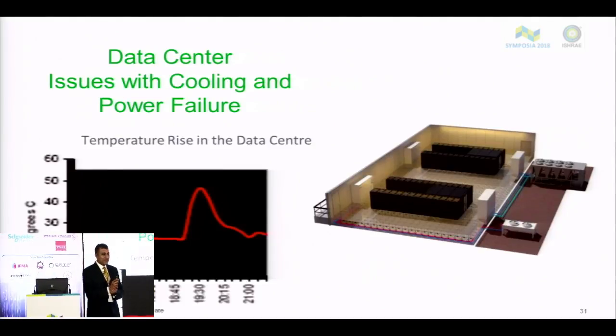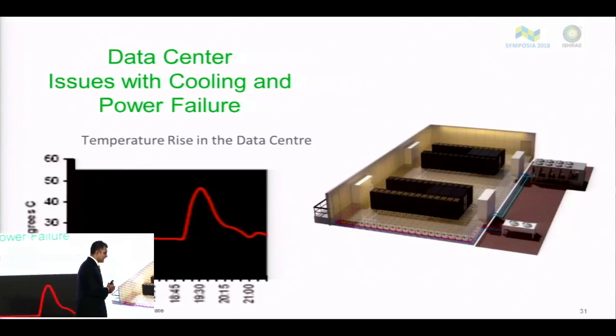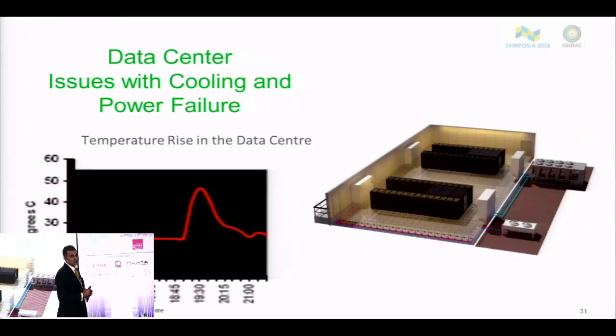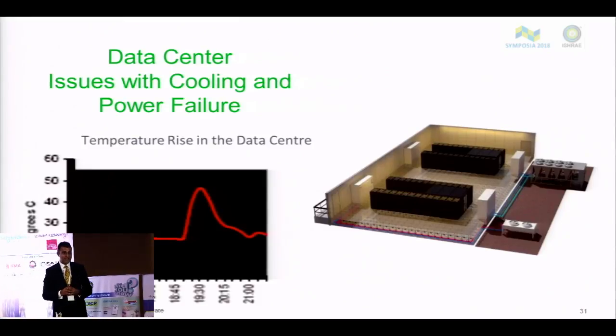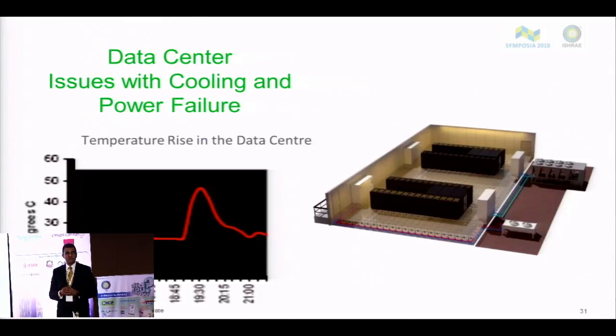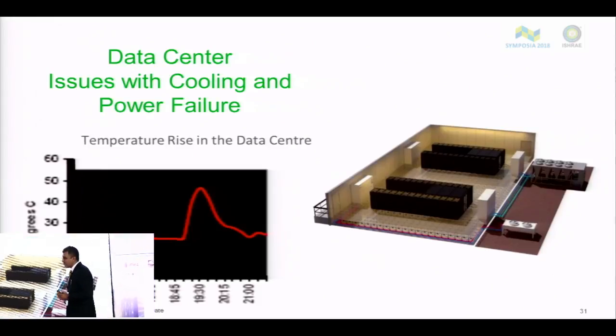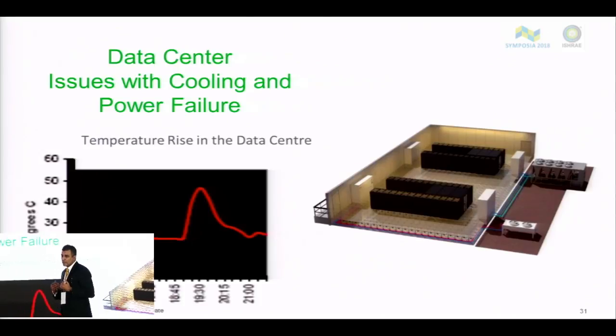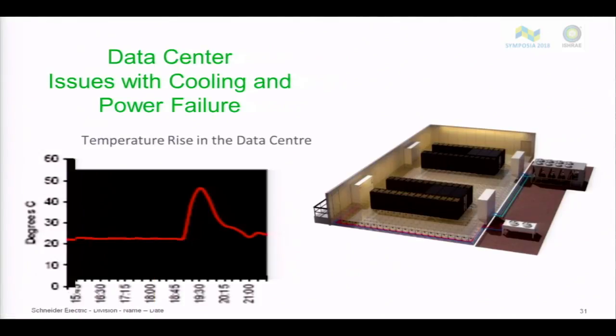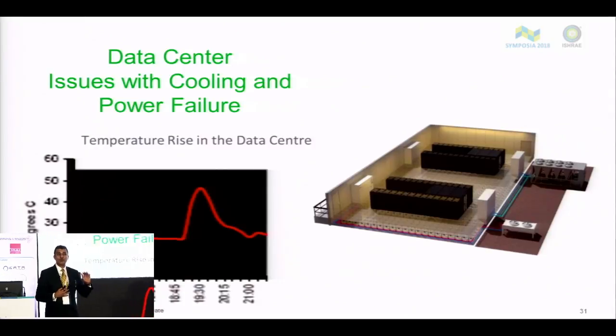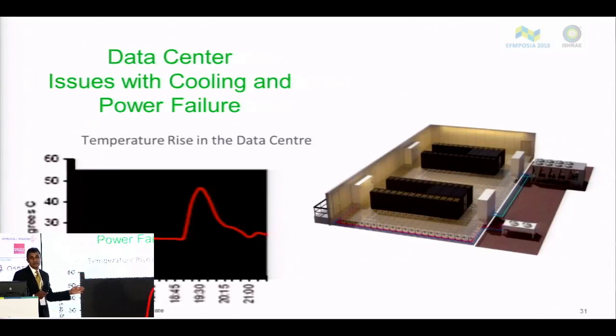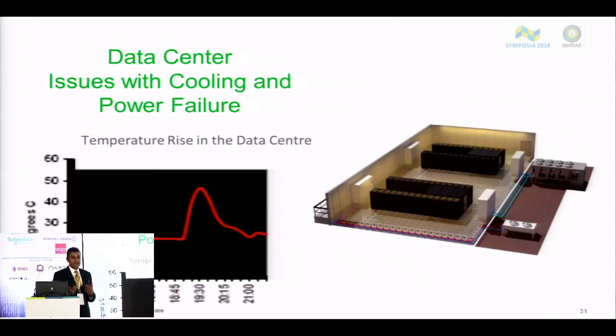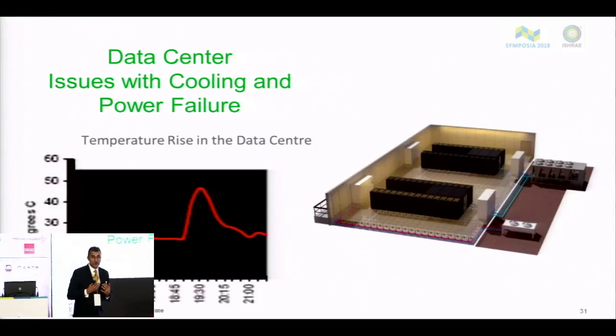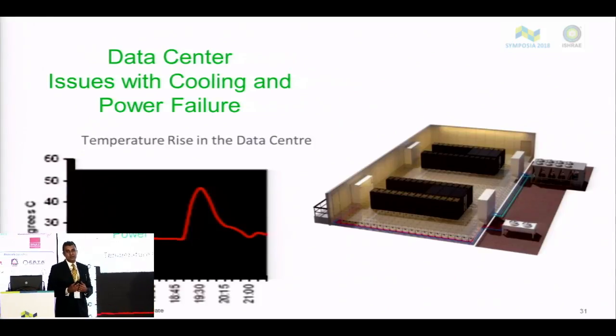With the ASHRAE thermal guidelines, we're now able to increase the on-rack temperatures for the chilled water systems or the cooling systems. We are able to increase the chilled water temperature itself also. One of the issues we see with higher densities in racks is the problem of cooling in the data center. It's more or less settled for the electrical distribution. More thought today is given to the cooling systems because it also offers a lot of efficiency. What we see here is a data center that's lost its cooling due to a grid failure, right? And it's important that we have the proper controls in place to mitigate the rise of temperature in the data center.